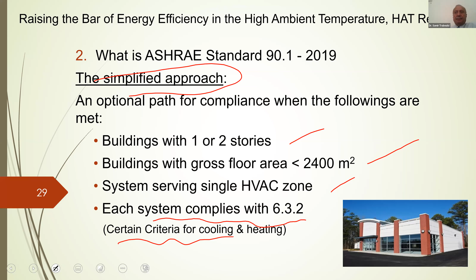The mandatory provisions come next, so if a building doesn't follow the simplified approach, we go into the mandatory. The mandatory tells you what sort of efficiency you need, what systems to use, package units, split units, chillers, how they're operated, furnaces, all based on the climate zone and the designer's decision on equipment and efficiencies. When these are mandatory, you have to follow them. If you violate them, you cannot proceed further. You have to prove to the authority that all mandatory provisions are met.